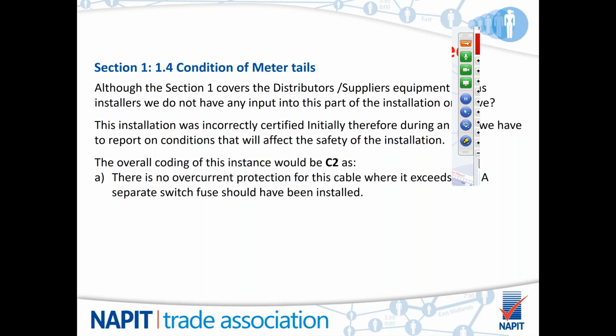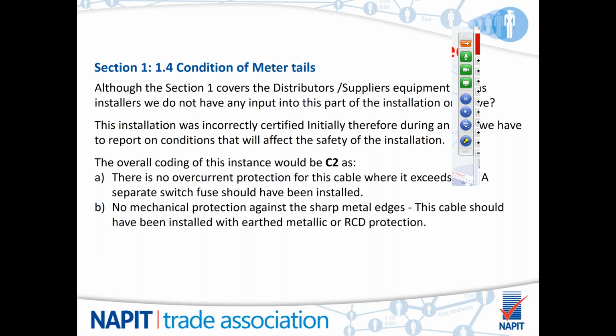First of all, with the length of the cables, there's no overcurrent protection for the cable. It exceeds 3 meters, and a separate switch fuse would need to be installed at the origin. There is no mechanical protection against the sharp edges of the metal frame. This cable should have been installed originally with some type of earth metallic covering or RCD protection.